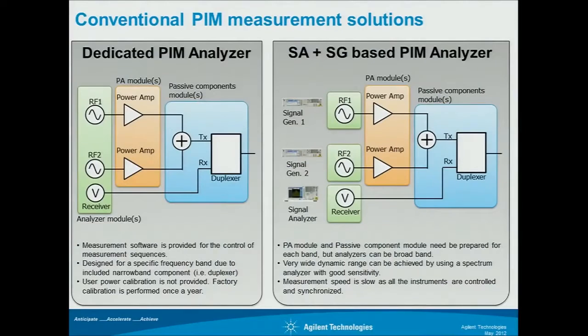Here are two conventional PIM measurement solutions. One is a dedicated PIM analyzer, and the other is an SA and SG-based PIM analyzer. The measurement idea is the same as the previous slide — we have two signal sources, two power amplifiers, combiners, and duplexers.